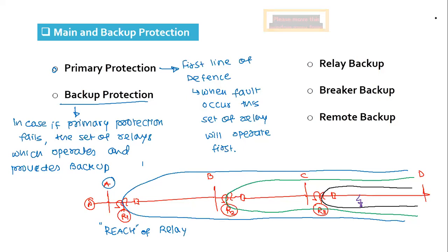So R3 should operate first and should trip this circuit breaker. Okay, R3 should operate first and trip the circuit breaker here. That is why R3 is the primary protection for line section CD. R3 is the primary relay.